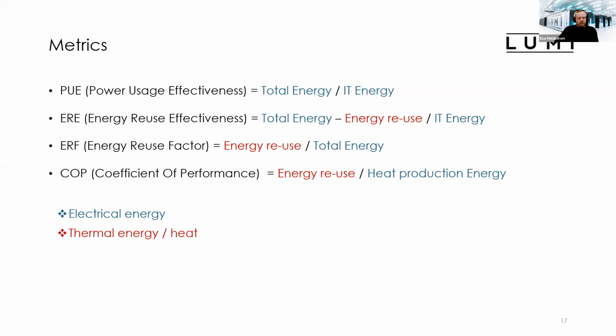Then about these metrics which we have. PUE is traditionally used to define the energy efficiency of the data center, but PUE is not a good measurement if the data center operates heat pumps by themselves for utilizing waste heat. It would be a huge difference if the waste heat can be utilized as it is, without priming it to higher temperatures with data center operated heat pumps.